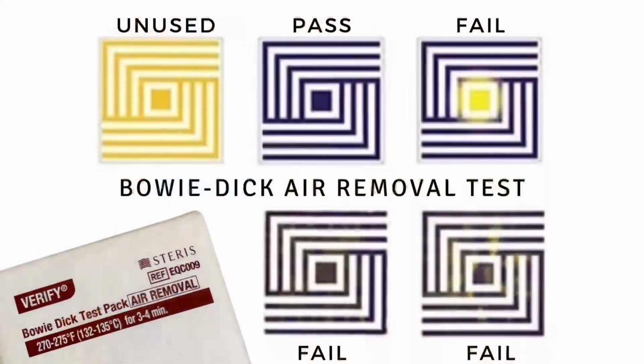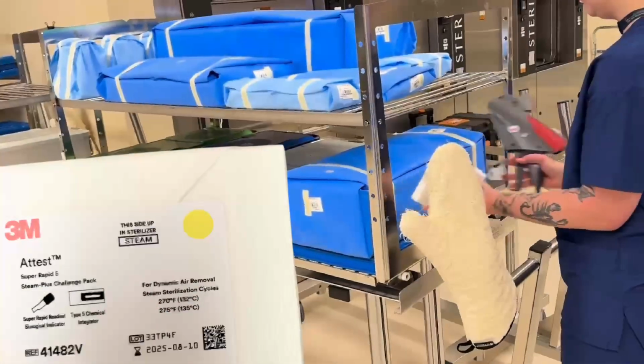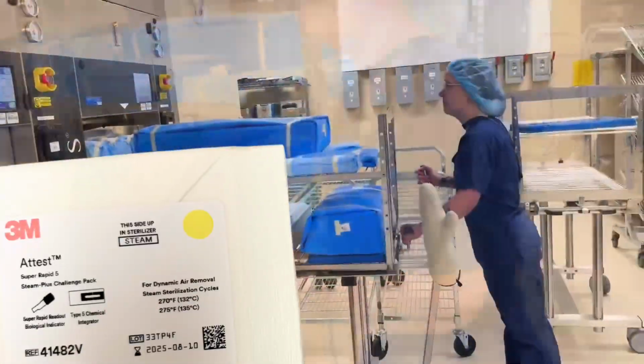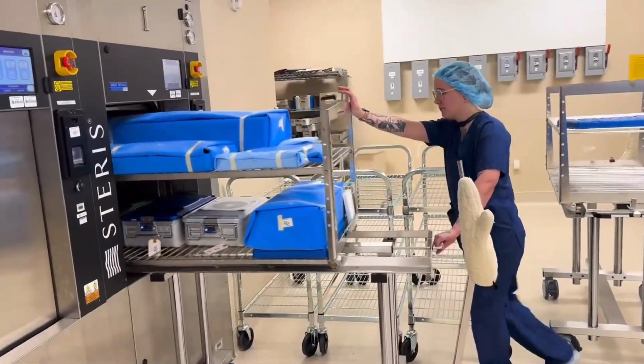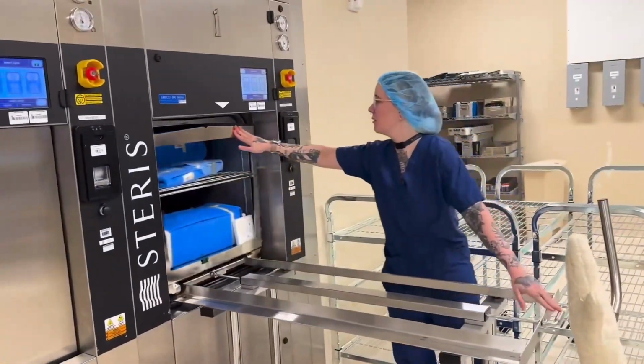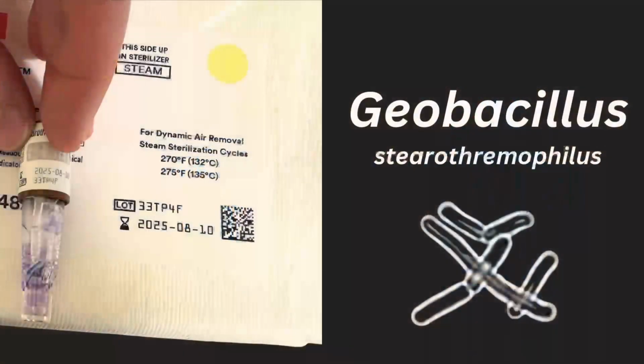For the first load of the day in each sterilizer, we ensure the autoclave meets air removal standards with the Bowie-Dick air removal test. The second loads of the day, loads with implants, or loads following a service, include a biological indicator spore test. Ours uses a liquid suspension of the endospores of Geobacillus stearothermophilus to determine whether the endospores are killed by the process.